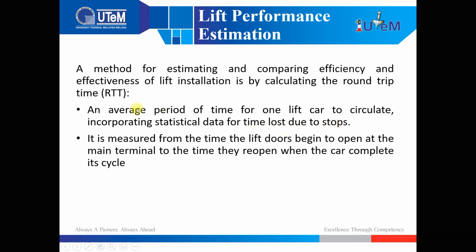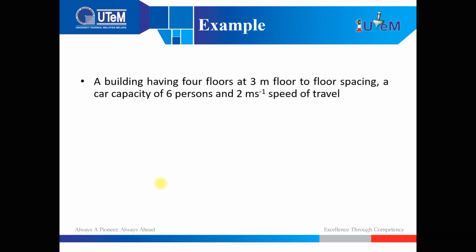Okay, this is the definition of the round trip time lah, and it is measured from the time the lift door begins to open at the main terminal to the time they reopen again when the car completes its cycle. So daripada pintu dia open sehingga dia buka balik. So that one is considered one trip ataupun one cycle. So we take a look at the example.